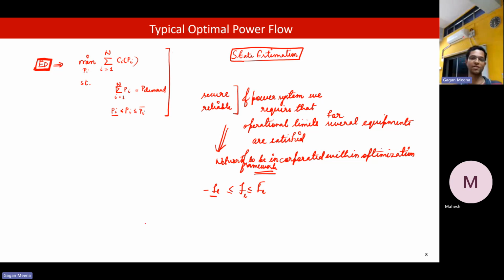So you always want to keep a safe buffer for any device. For every device, for a line, we have a maximum and minimum limit. We want voltage to be within a lower and upper bound, which may be 1.05 to 0.95 per unit. We don't want voltage collapse to happen.